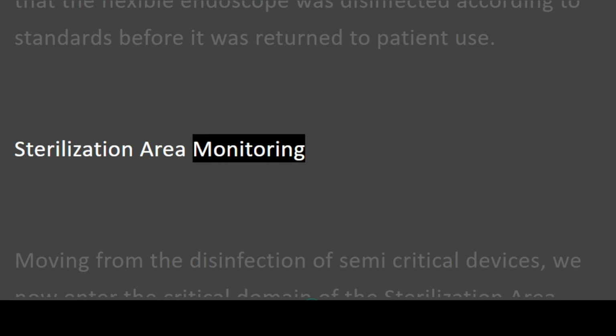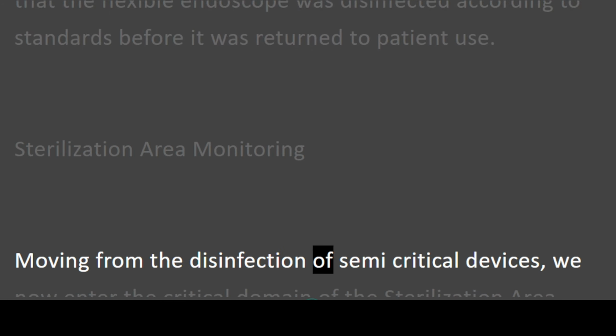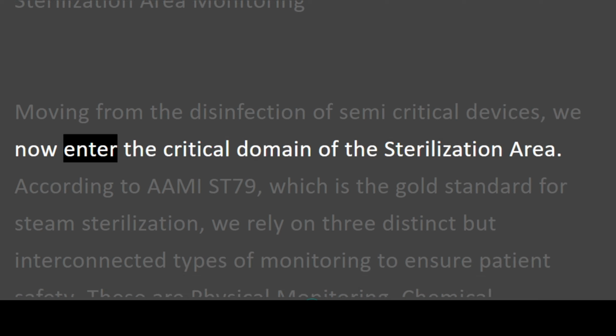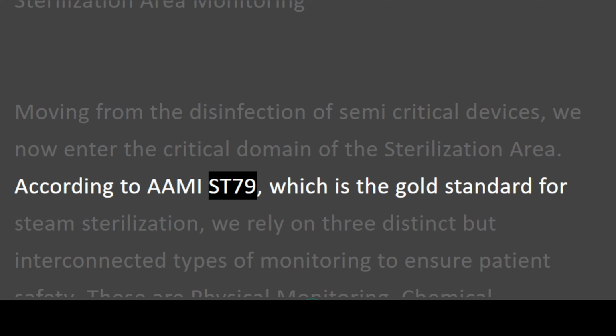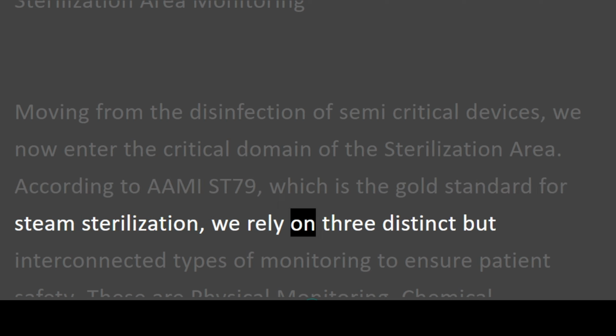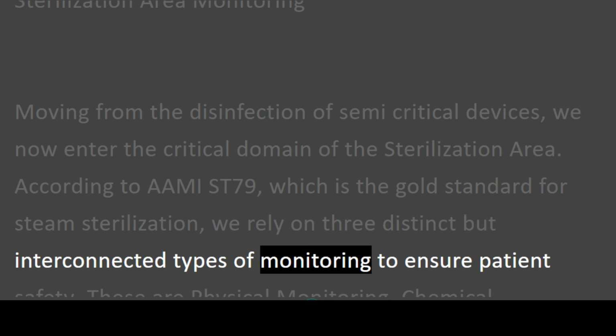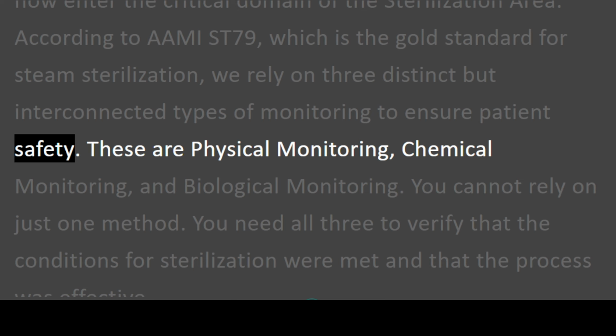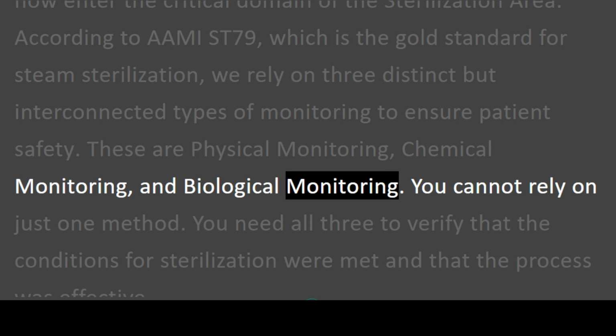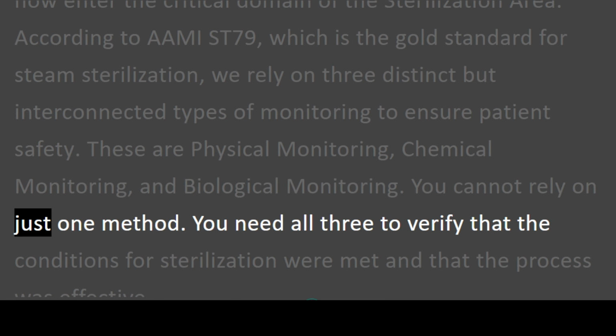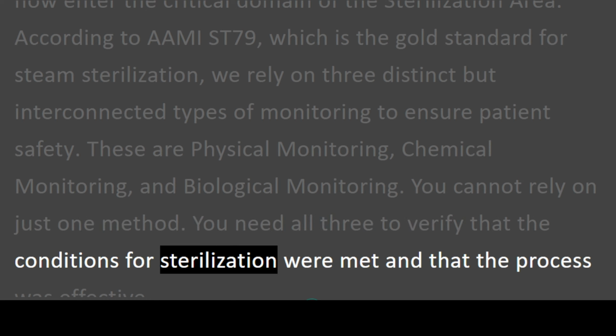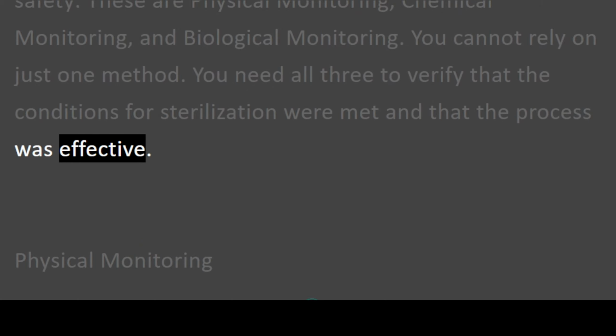Sterilization area monitoring. Moving from the disinfection of semi-critical devices, we now enter the critical domain of the sterilization area. According to AAMI ST79, which is the gold standard for steam sterilization, we rely on three distinct but interconnected types of monitoring to ensure patient safety. These are physical monitoring, chemical monitoring, and biological monitoring. You cannot rely on just one method. You need all three to verify that the conditions for sterilization were met and that the process was effective.